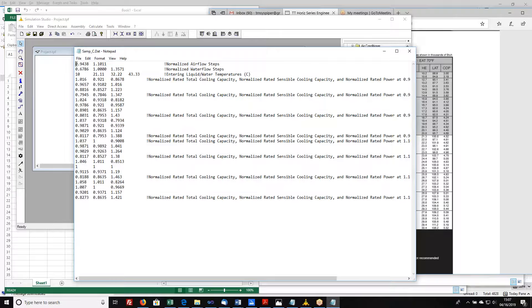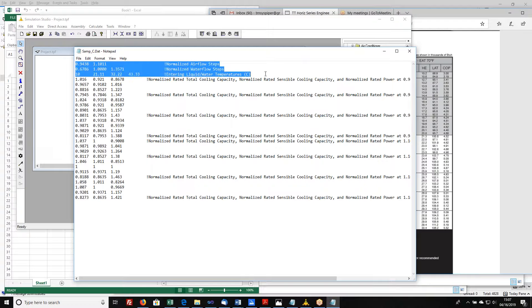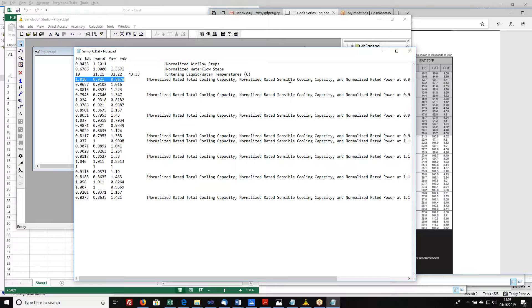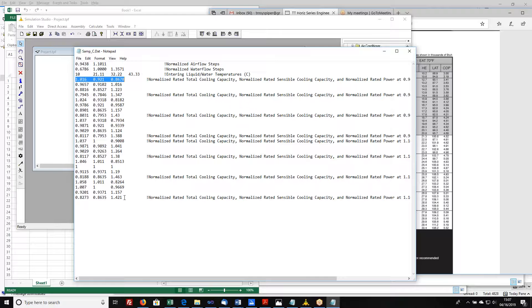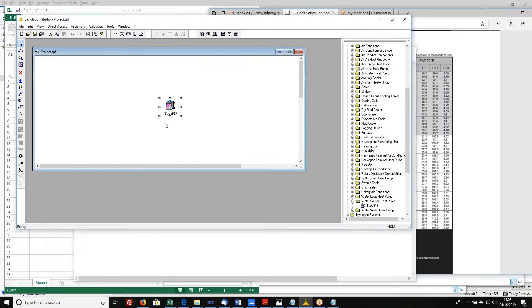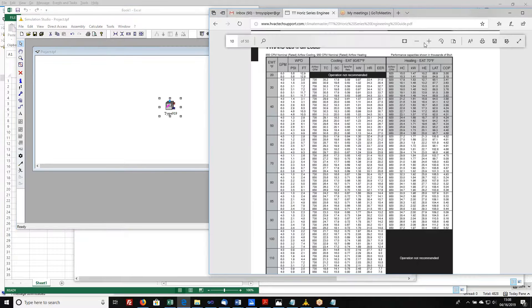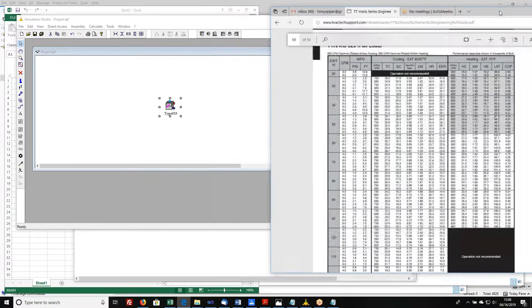This particular file has three independent variables. These are sort of the things that we know. These are the inlet conditions to this heat pump. Then it's got three performance metrics, three dependent variables. In this case, it is the normalized total cooling capacity, normalized sensible cooling capacity, and normalized power at a certain combination of these independent variables. What I'm going to show you is how you actually create this data file based on something that you would find in a manufacturer's catalog data. So as I said, this is a heat pump. It is a water source heat pump. So it's got air on the load side and it's got water on the source side.